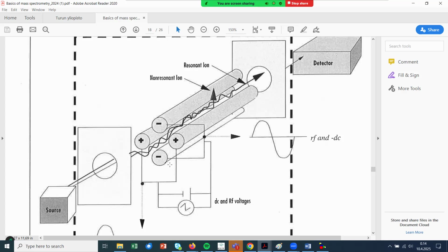And this is the way the analysis takes place. We always know, or the instrument, the software knows, what the settings are. And if it's a certain ion fitting the settings and being exactly of this certain mass-to-charge ratio, M to Z, if it's present, it's let fly through with those settings that are unique to this. If it's not there, you don't see any signal.